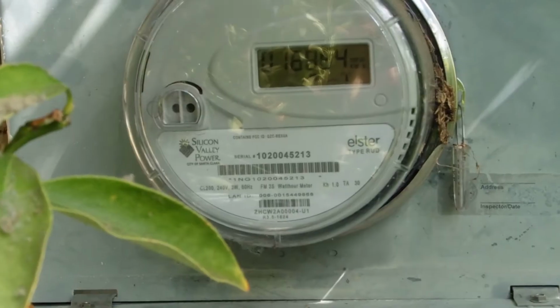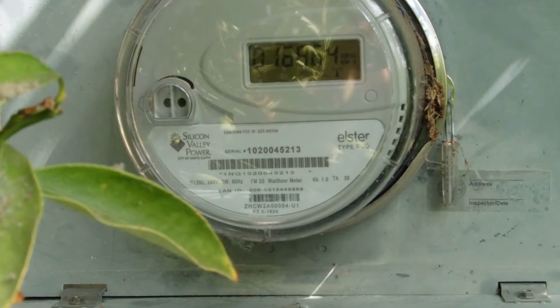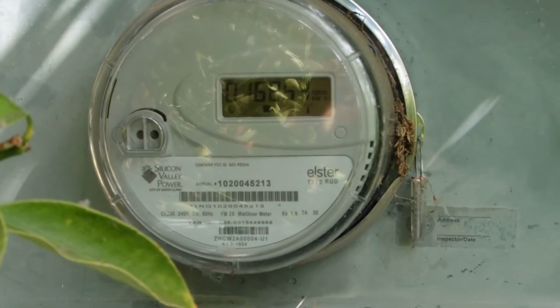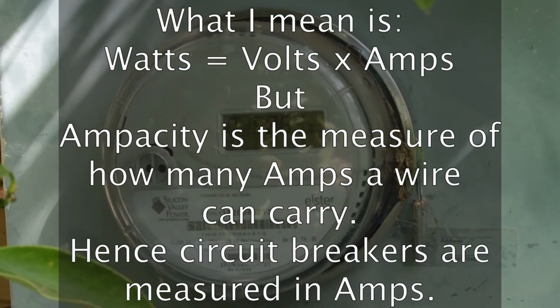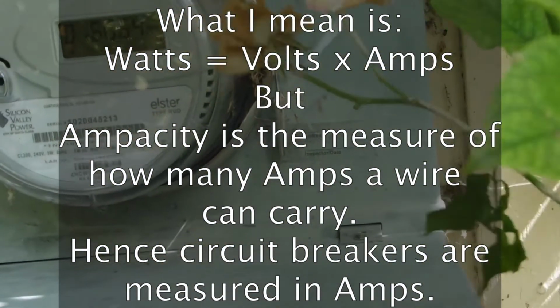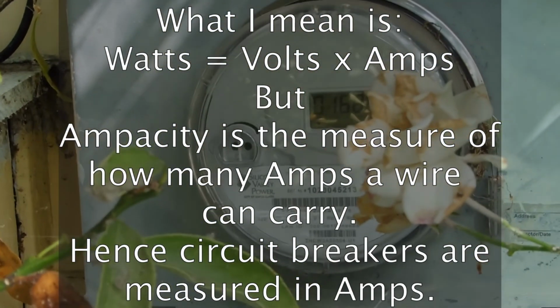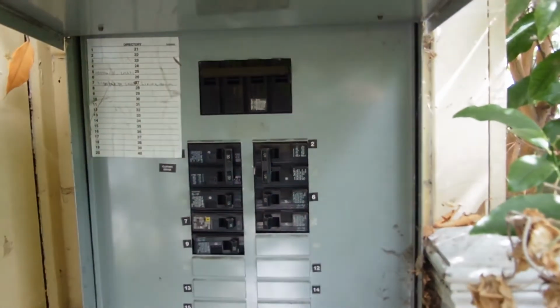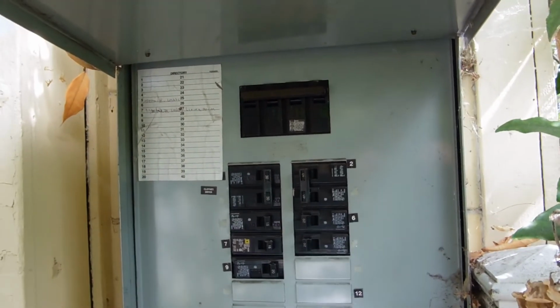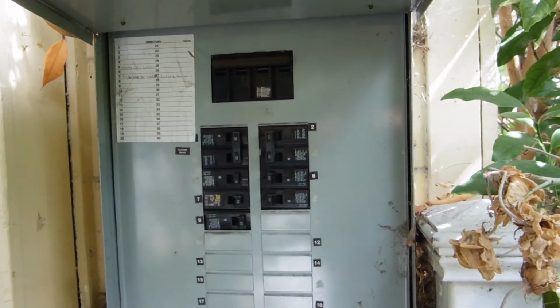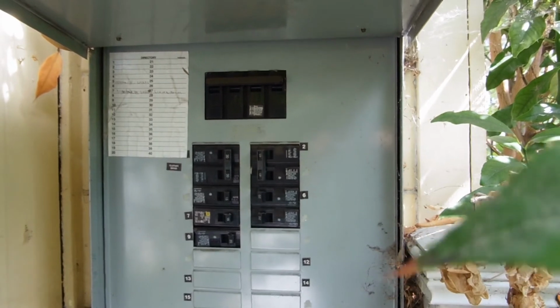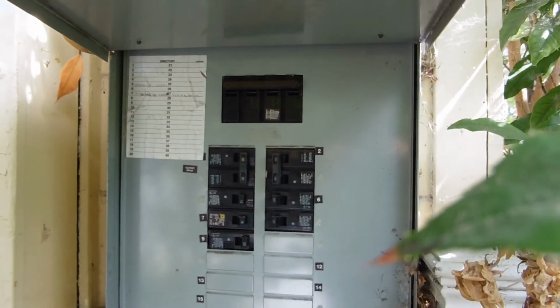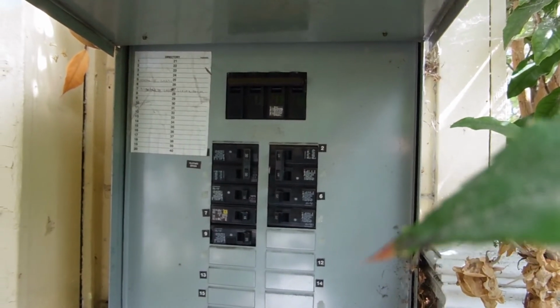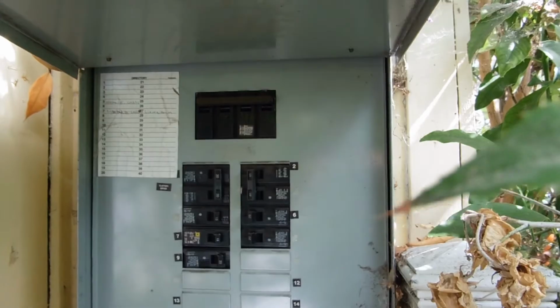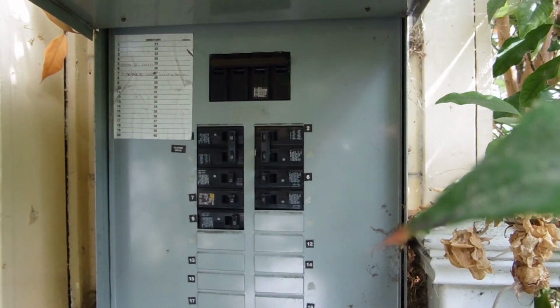This is the electricity meter, and apparently on this there is some kind of label showing how much power it's able to handle. Electricity power is measured in amps. The service is 240 volts, but the capacity is rated in amps. So that's what we need to look at down here. Each of these is a circuit breaker that governs how much electricity is available at the house. At the top is the master circuit breaker, and somewhere on there, but I don't see it, is the maximum rating for the master circuit breaker. And then below that are the circuit breakers for each circuit.